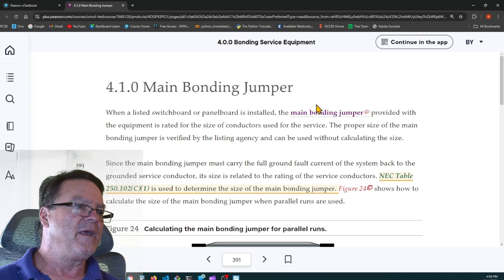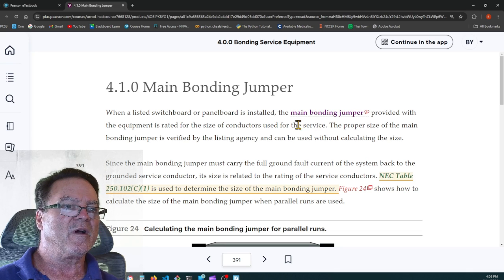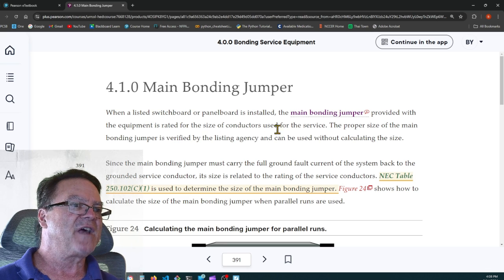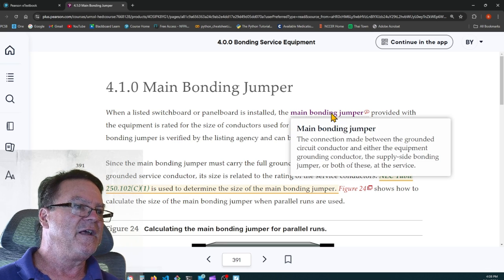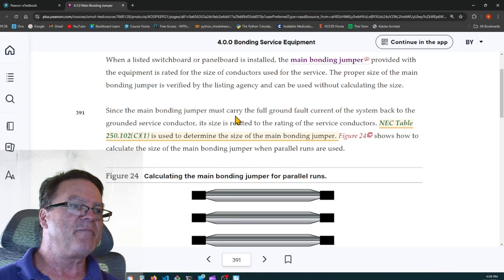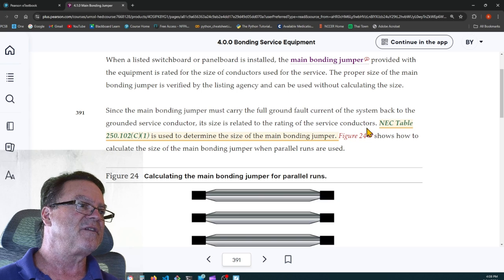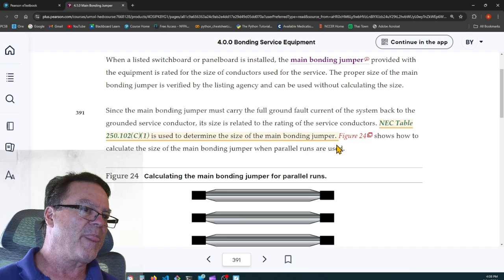Main bonding jumper. When a listed switchboard or panel board is installed, the main bonding jumper is provided with the equipment, provided the equipment is rated for the size of the conductors used for the service. Main bonding jumper is a connection made between the grounded circuit conductor and either the equipment grounding conductor, supply side bonding jumper, or both of these at the service. Here's a highlight. It says, since the main bonding jumper must carry the full ground fault current of the system back to the grounded service conductor, its size is related to the rating of the service conductors. NEC table 250.102C1 is used to determine the size of the main bonding jumper. And it goes by the size of the ungrounded conductors.